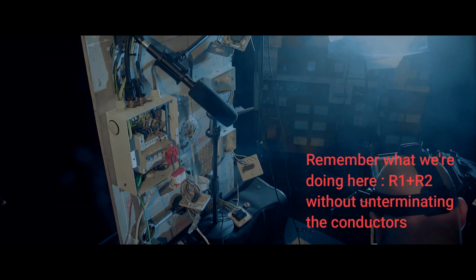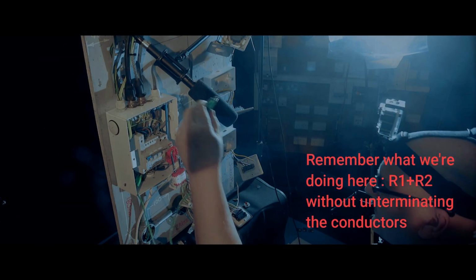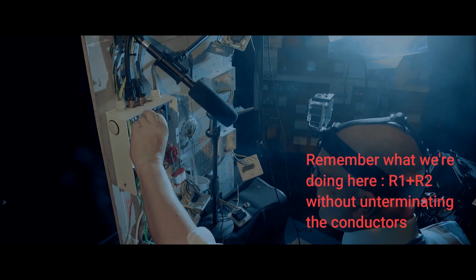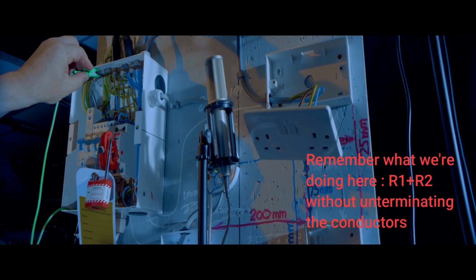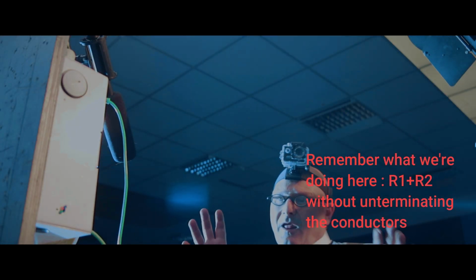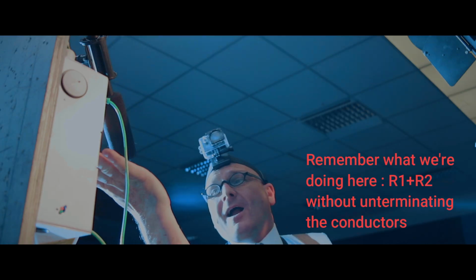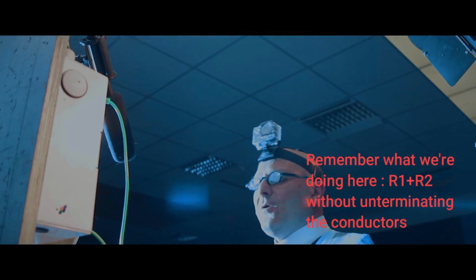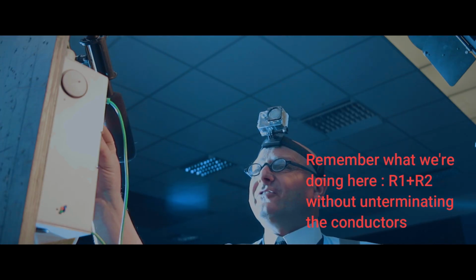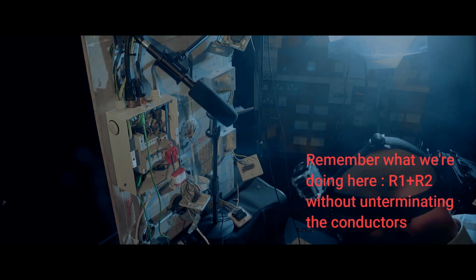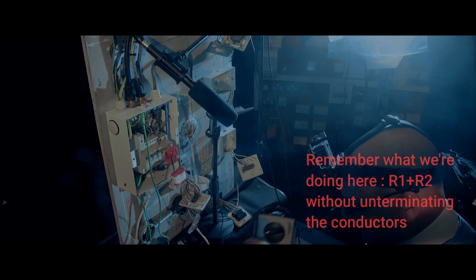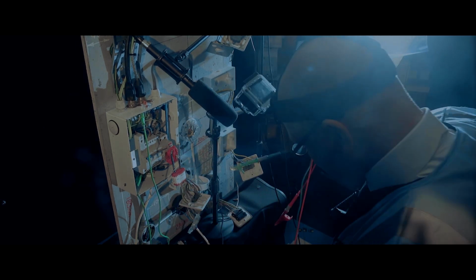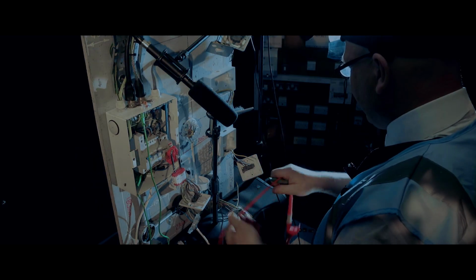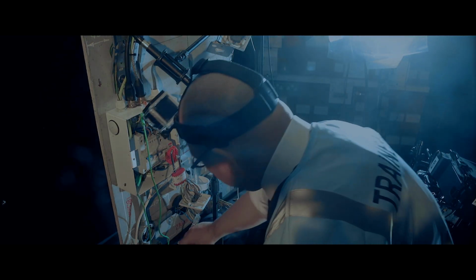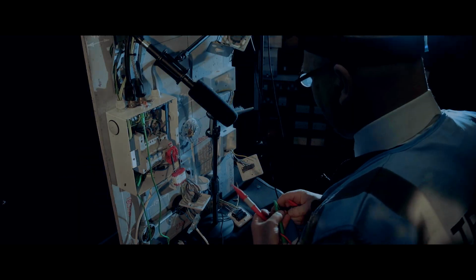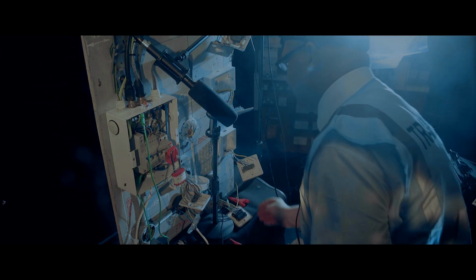I can now connect all the origins of those brown cables to all the origins of the CPCs up there. Instead of taking out my line conductor and Wago-ing it to a CPC individually, I can now take my multifunction tester with probes to the back of my end of line, wherever that may be, ceiling rose.